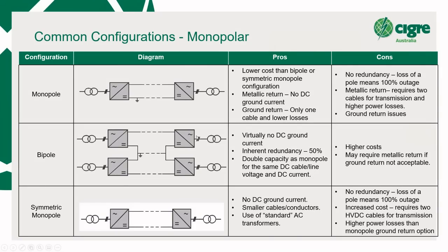Right, common configurations. So still talking about HVDC in general, but we have common configurations here: monopole, bipole, symmetric monopole. And some people will be quite used to these terms. But just very quickly, a monopole has one high voltage conductor here and an earth return. Now that return is either through the earth, as shown here, but with the dashed line, it can also be a metallic return if ground current is, for whatever reason, not possible.